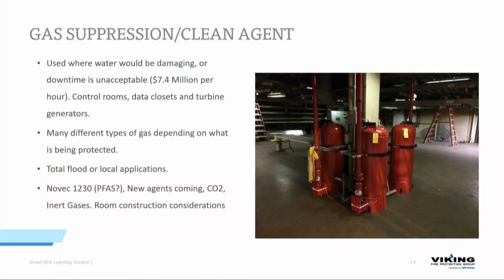Kelly, what's the upkeep on this? Good question. So if we just take, for example, these 3 tanks right here, feeding up to a control room, whatever it is. Every year, we're going to come in and do an annual inspection. We're going to test the alarms. We're going to test the integrity of the piping. We're going to pull these tanks off of whatever they're connected to and weigh them to make sure that the agent is still in there, that the agent hasn't leaked, that those numbers are the same as the year before. So pretty much it's either an annual or a semi-annual inspection on most gas suppression systems, depending on the owner, authority having jurisdiction, or insurance company.